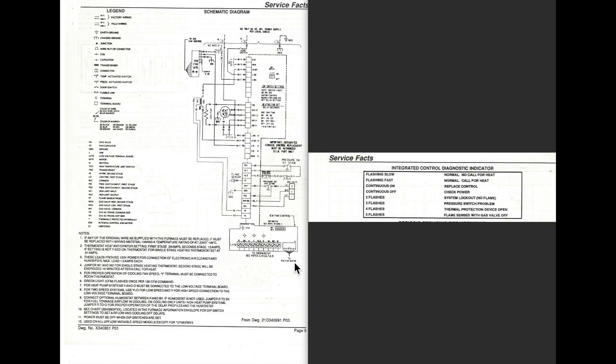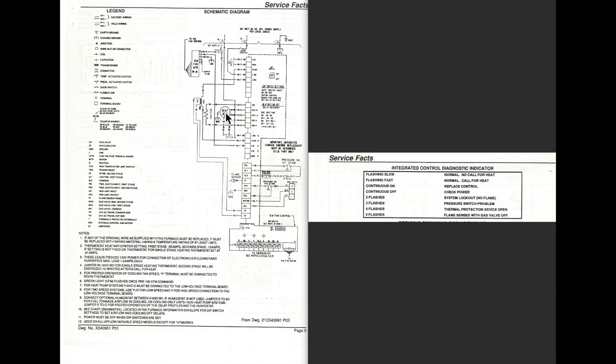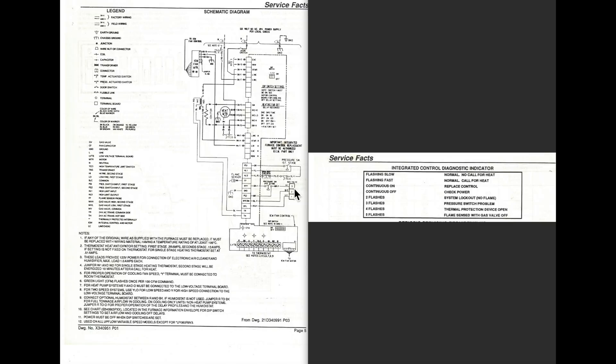If we go to second stage, we've got a second stage pressure switch here. So what's going to happen is W2 is going to be energized down here at the terminal board. That's going to tell the board we want second stage heat, so the vent motor is going to go up to high speed, and this pressure switch, the second pressure switch here for second stage, is going to close, and the power is going to go to the high fire of the gas valve, and the gas valve is going to go to high fire. Well, you notice there's a second wire here. That goes back to the board and tells the fan motor to go to the second stage heat, which is a higher speed.